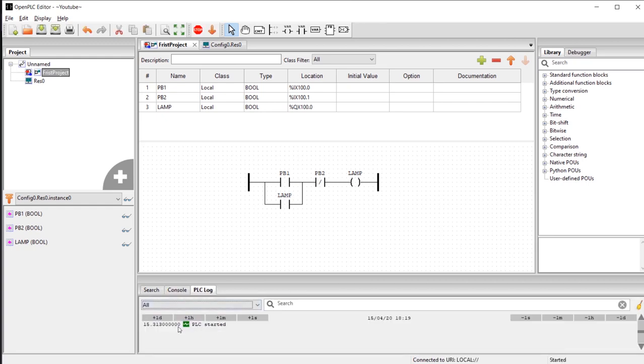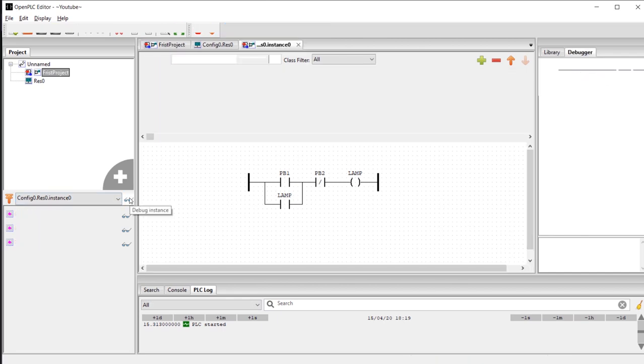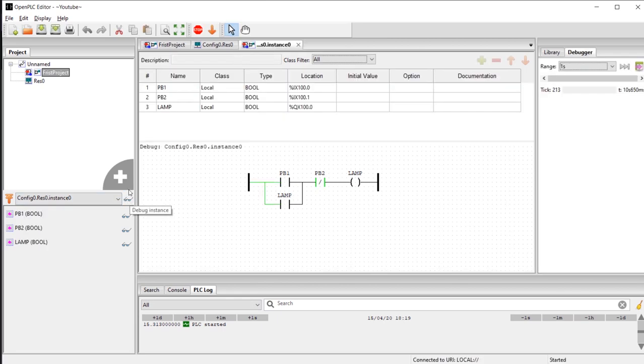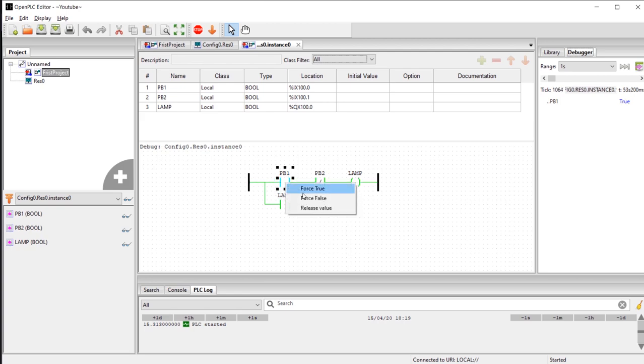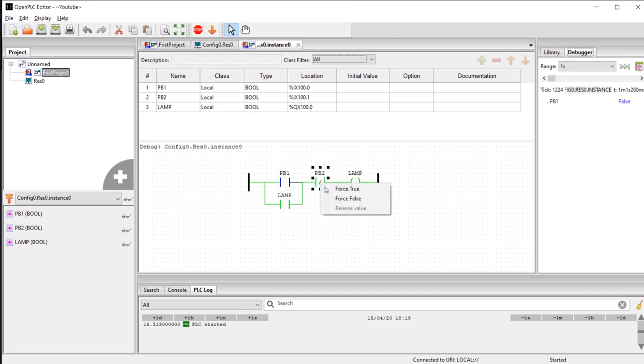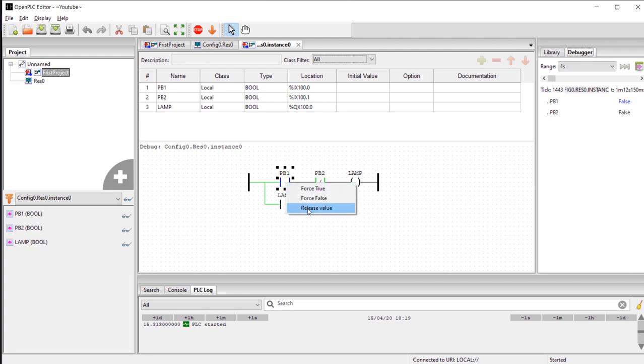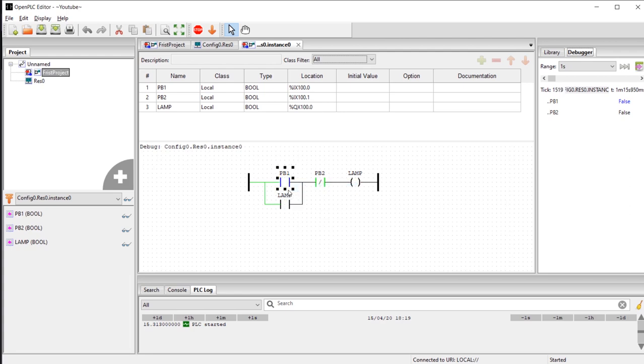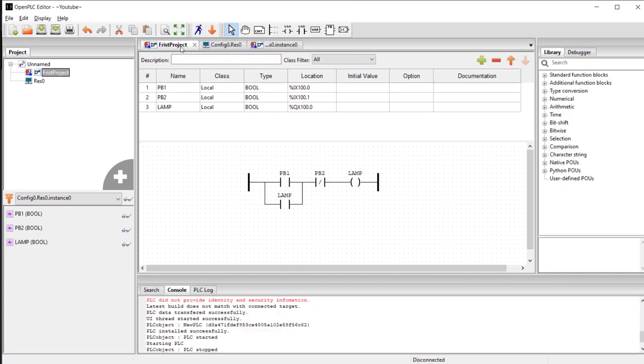If you click the running man icon, you're going to start generating the code. It tells you the PLC started, so the simulation is running. To enter the simulation tab, you need to click on the debugging instance, this glasses icon. So to start debugging, let's right-click it: force true. So now basically you push the button. Force false—you stop pushing the button. However, because there's a latch here, the lamp is still running. If we push that, now it's open circuit, everything stopped. Now we can just release value here.